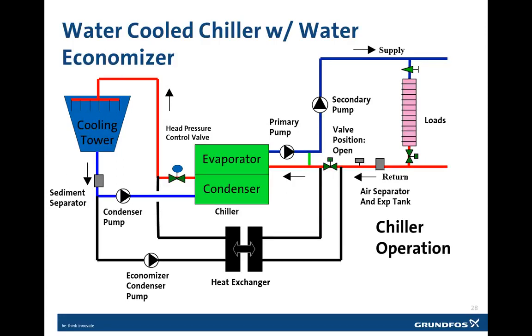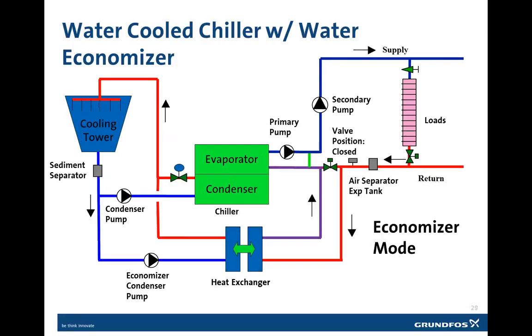Now the system is not altered when the operation temperatures of the hot and cooling water demand are high, and the cooling chiller and the cooling tower operate. The economizer is then ignored. Now, when outside air temperatures are temperate, so below about 50 degrees dry bulb and about 45 degrees wet bulb, the work done by the chiller can be decreased as a result of the free cooling, because the cooling tower's evaporative cooling can then achieve a low enough water temperature to reduce the entering water temperature into the chiller. Now, this is considered a water economizer.